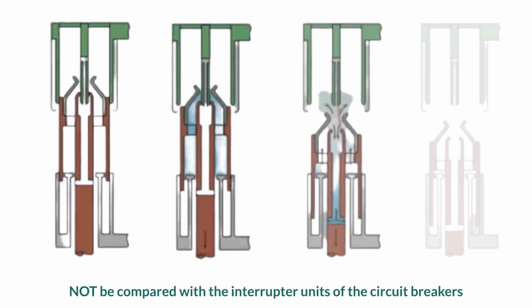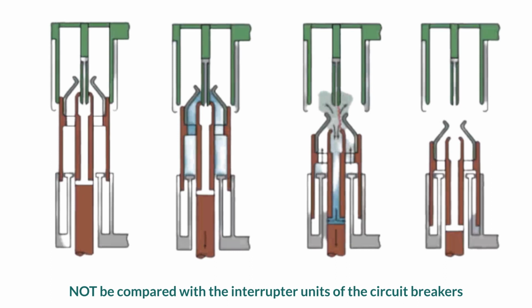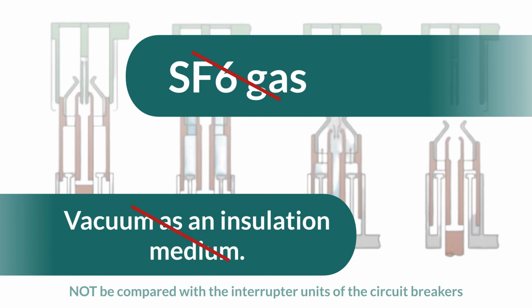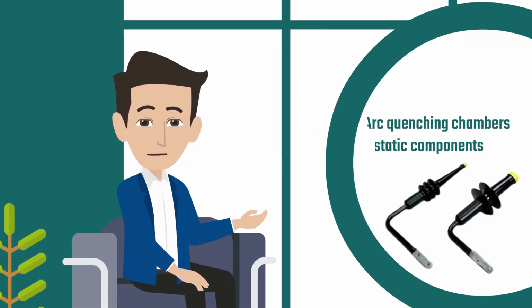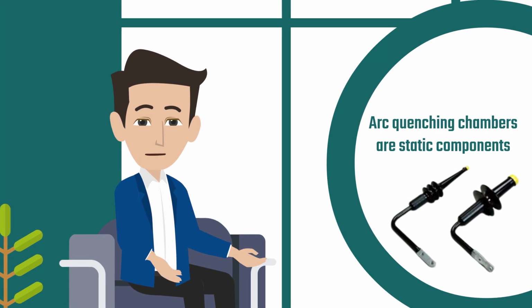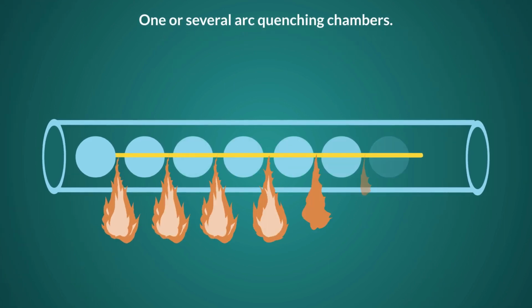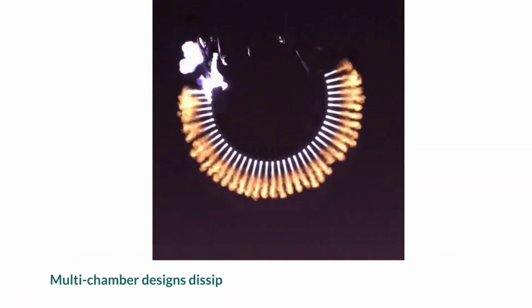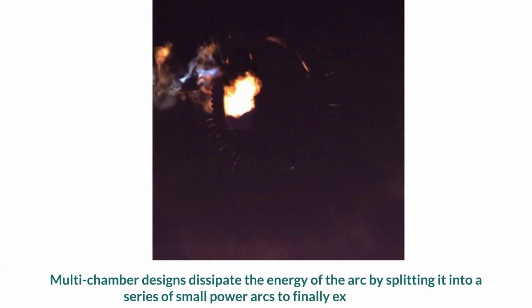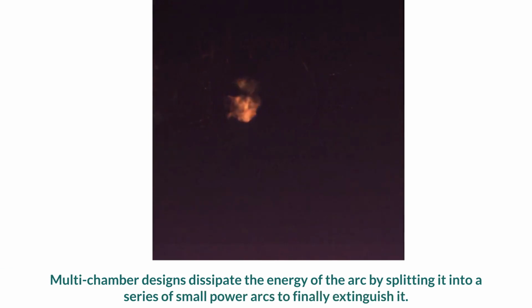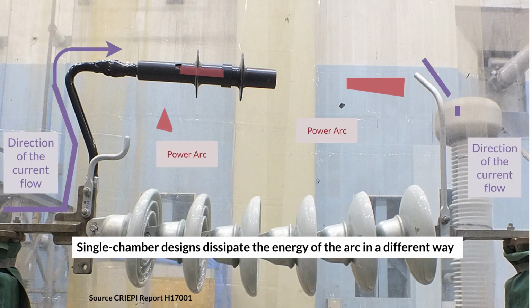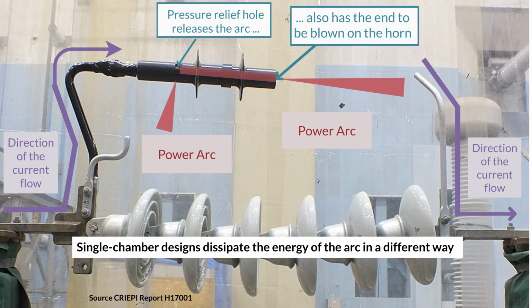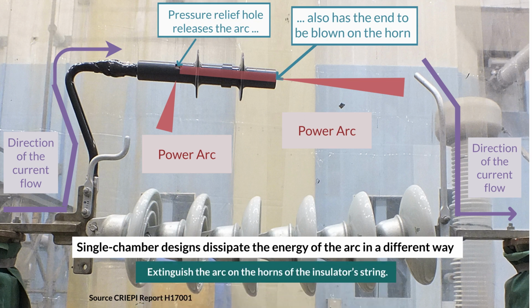It should not be compared with the interrupter units of circuit breakers, which consist of an active extinction mechanism, often combined with SF6 gas or vacuum as an insulation medium. Arc quenching chambers are static components and have this extinguishing capability by design, without any active mechanism. There are different designs made of one or several arc quenching chambers. Multi-chamber designs dissipate the energy of the arc by splitting it into a series of small power arcs to finally extinguish it. The single-chamber designs dissipate the energy of the arc in a different way, thanks to two holes at the extremities of the active part that project and extinguish the arc on the horns of the insulator string.